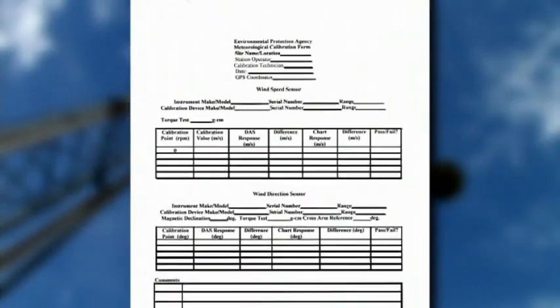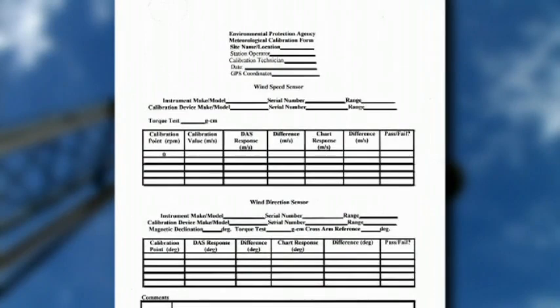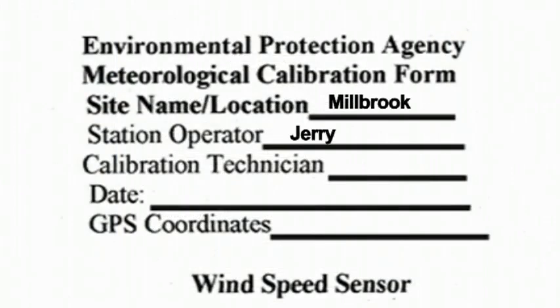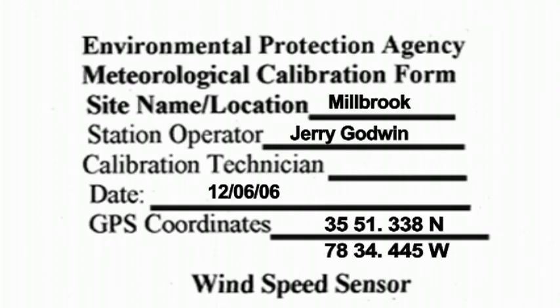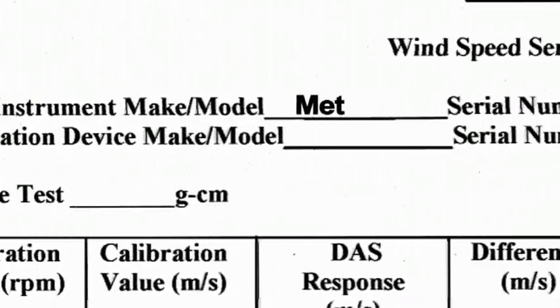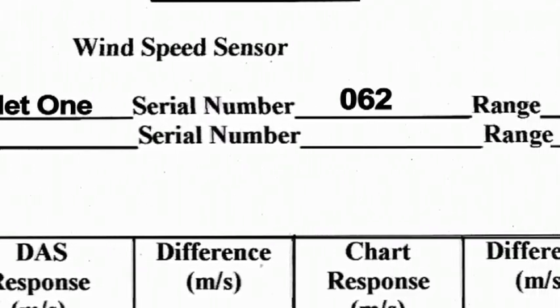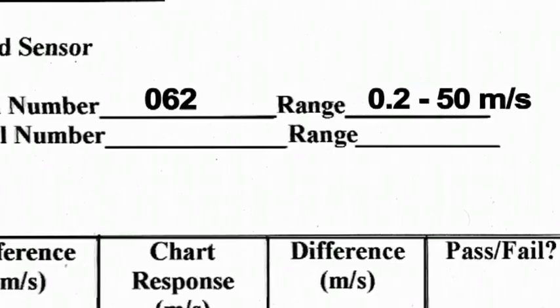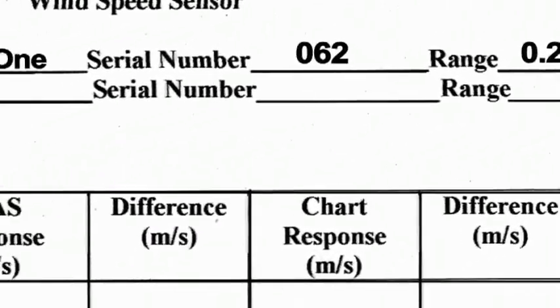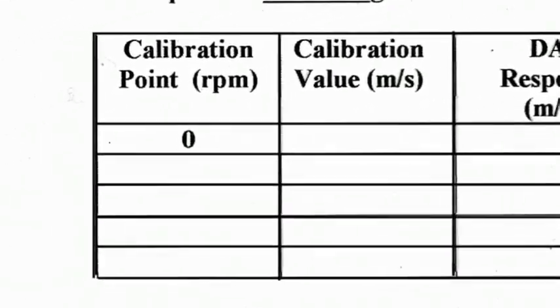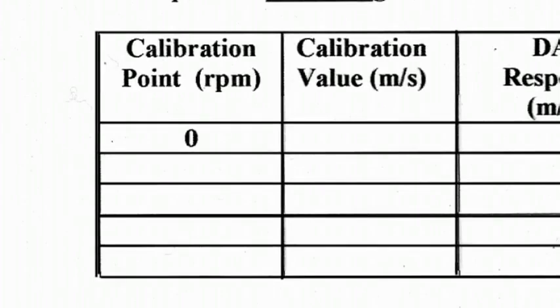It is now time to begin the calibration. Calibration data should be recorded on a calibration sheet and in the station log book. The first task is to record the location, operator, date, and GPS coordinates. The second task is to record the instrument make, model, serial numbers, and full-scale range. You will note that the form has two sets of tables. The first column in the top table should read calibration points, RPM. The second column should read calibration values in meters per second.